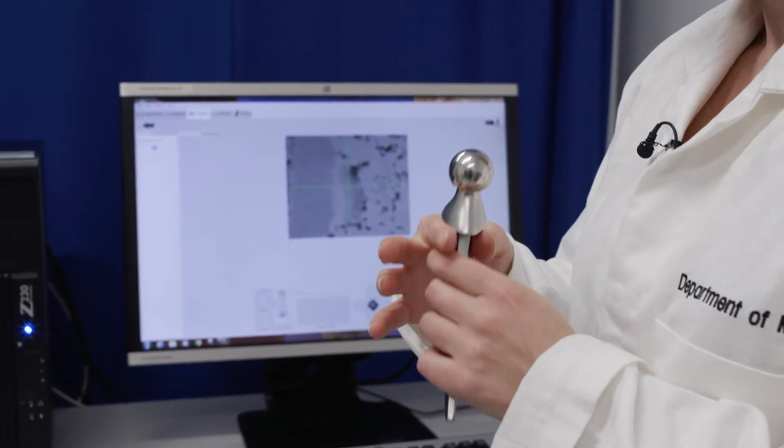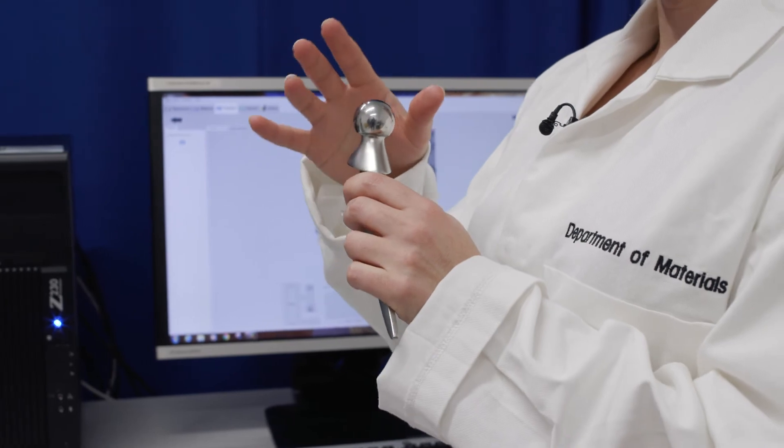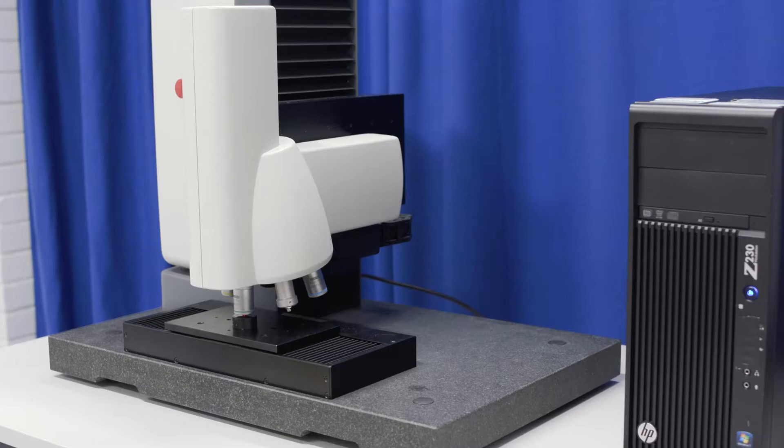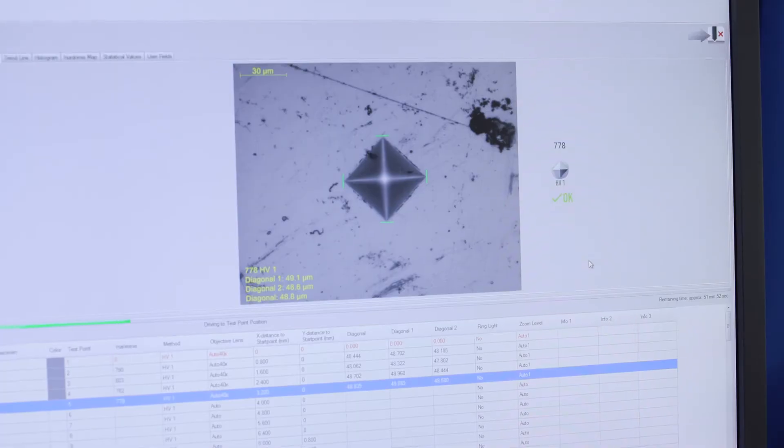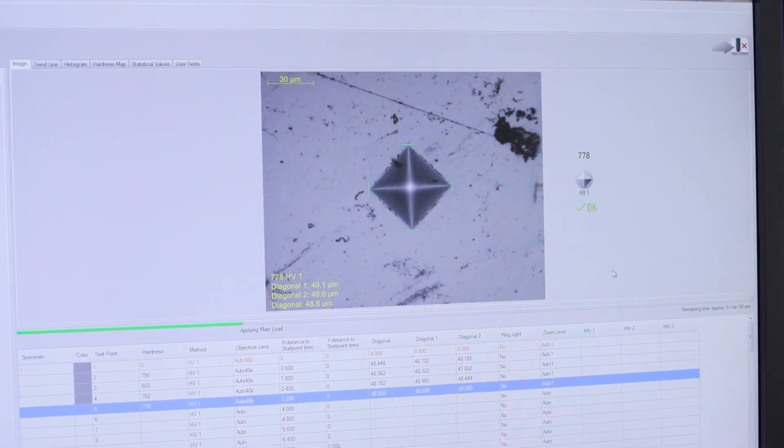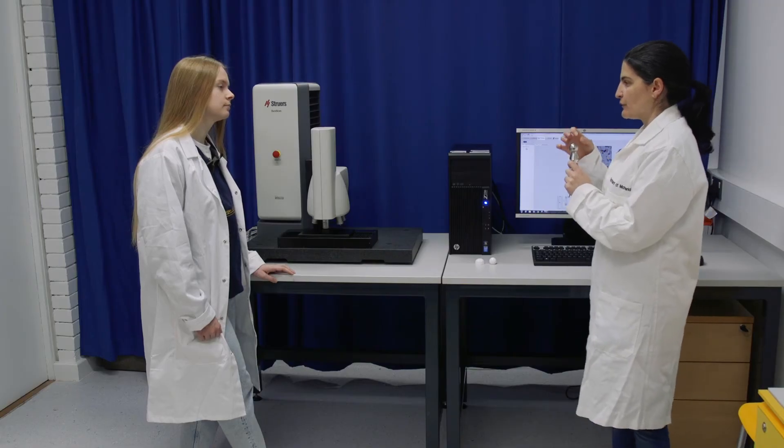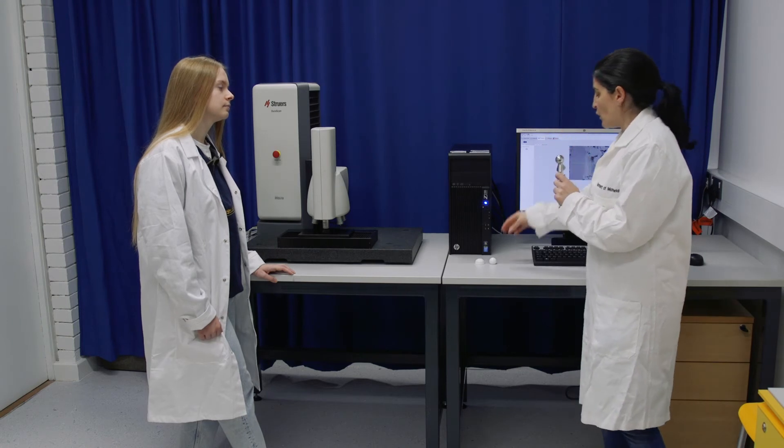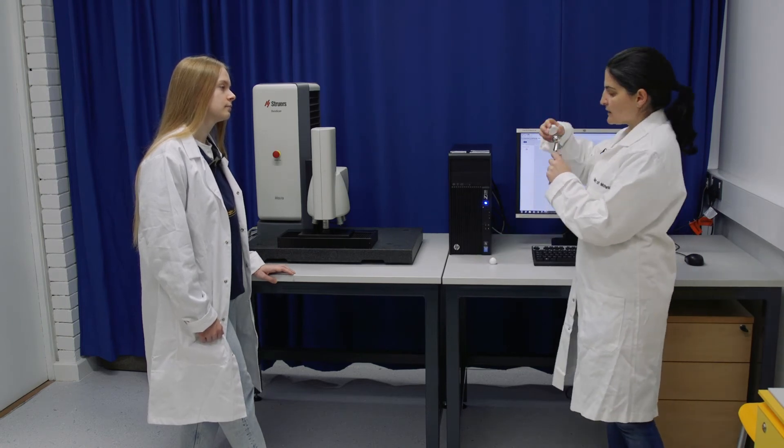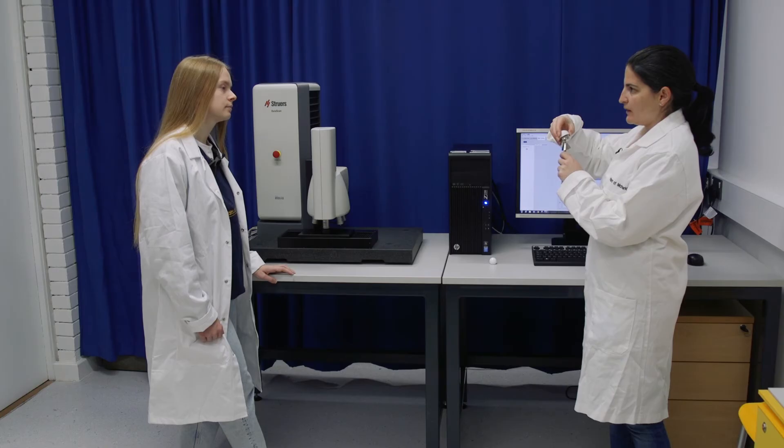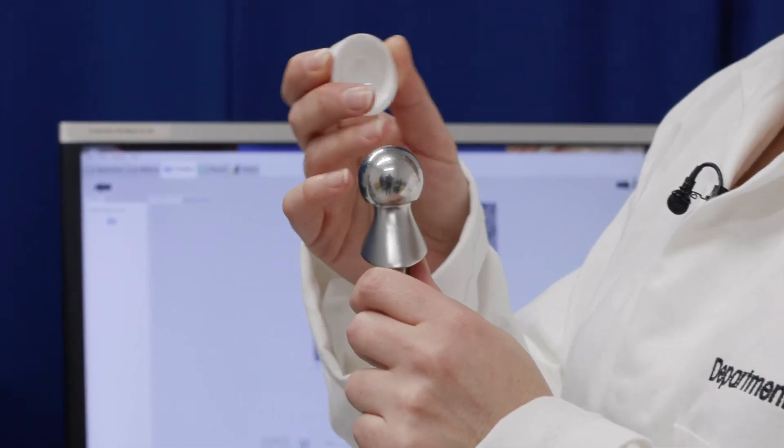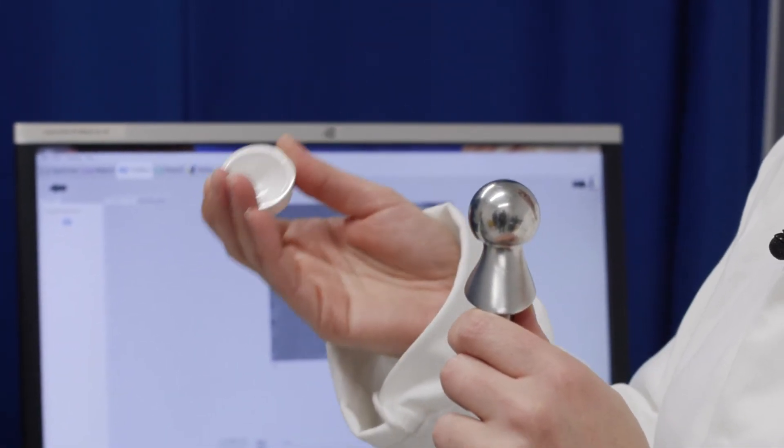Another type of test that is very important for hip implant is a hardness test. This is a system that we use. We study if there is a release of particles—very small bits of the implant are released when the cap is going to be in contact with the head. If those particles are released, they can create a problem like inflammation in the human body.